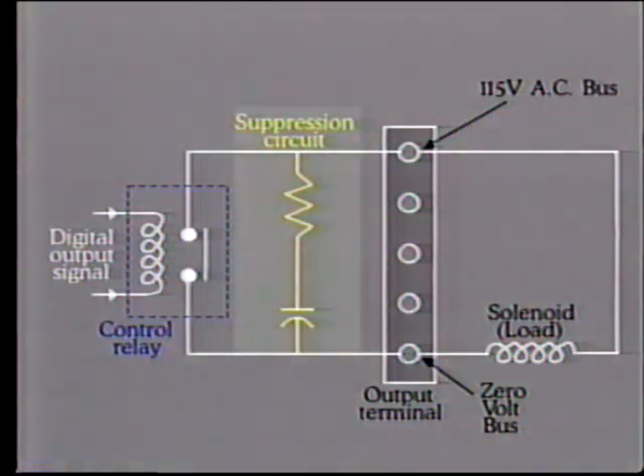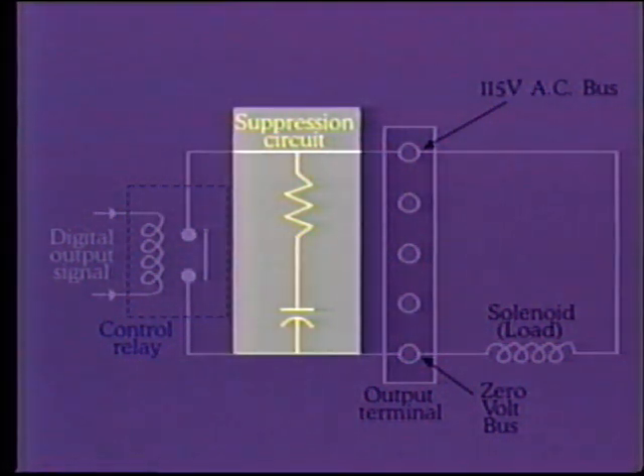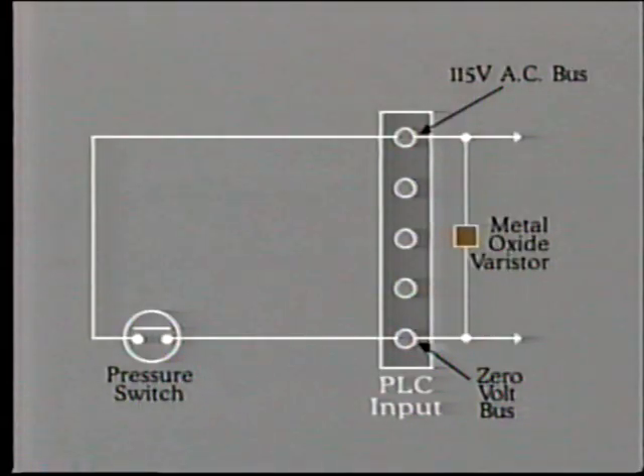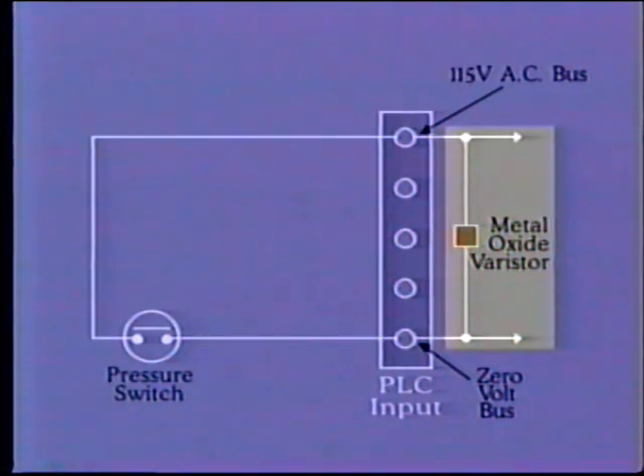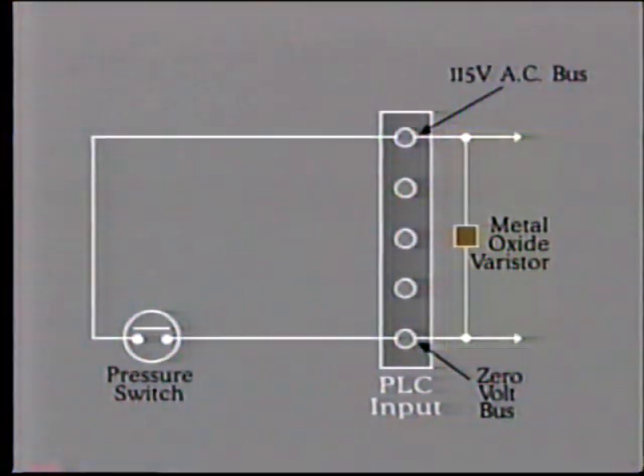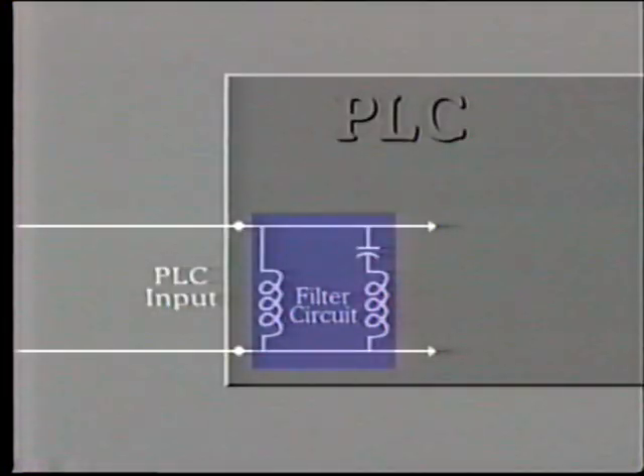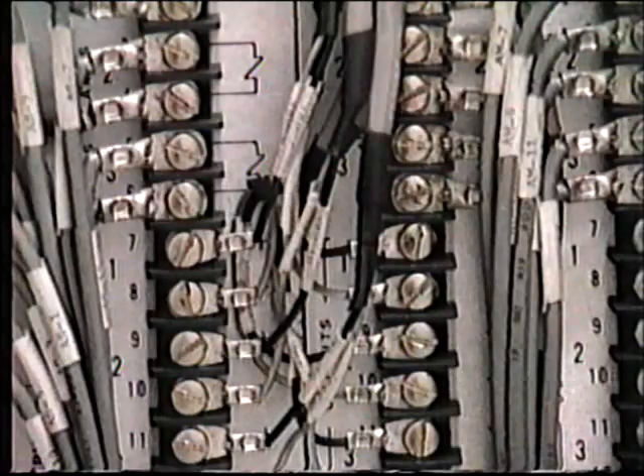This circuit consists of a capacitor and resistance in series. Additionally, MOVs, that is, metal oxide varistors, are connected across input devices so as to absorb voltage spikes. Filters can be connected to reject 50 or 60 hertz interference, that is, AC line hum. Shielded cables should be used throughout, and all grounding should be made at a single point only.